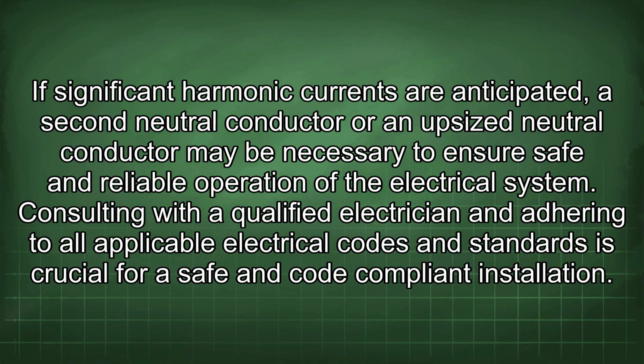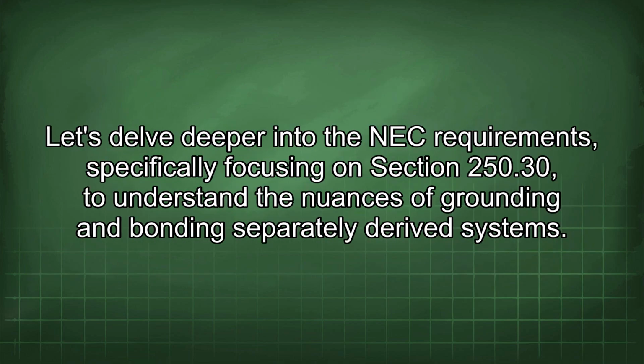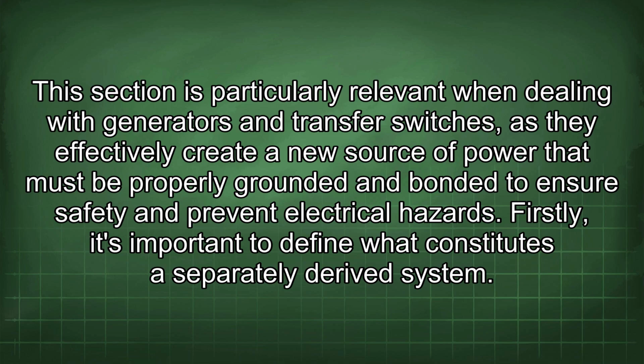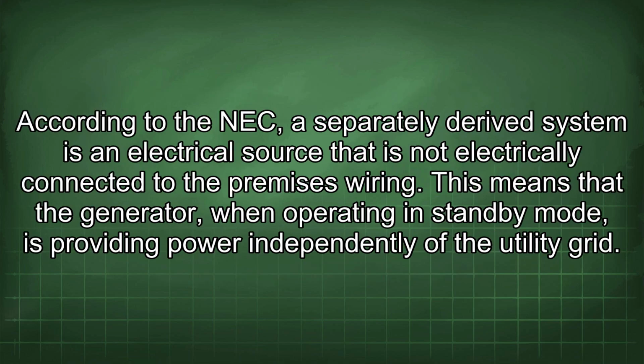code-compliant installation. Let's delve deeper into the NEC requirements, specifically focusing on Section 250.30, to understand the nuances of grounding and bonding separately derived systems. This section is particularly relevant when dealing with generators and transfer switches, as they effectively create a new source of power that must be properly grounded and bonded to ensure safety and prevent electrical hazards. Firstly, it's important to define what constitutes a separately derived system. According to the NEC, a separately derived system is an electrical source that is not electrically connected to the premises wiring.